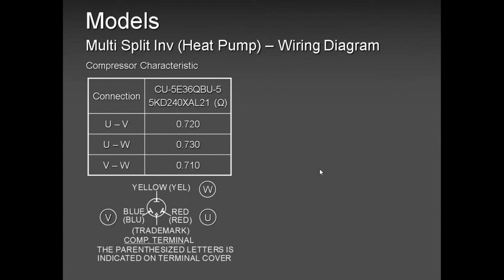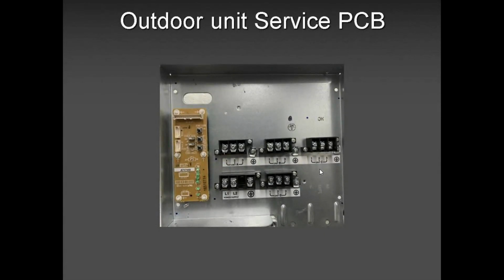When you have a problem, or when you think you have a problem with a sensor, just open up your app or your service manual, and you will see all these values. Take your multimeter, not an amp probe. Okay, don't use your amp probe meter. Use your multimeter. It will give you better, appropriate, correct readings, and compare them to the chart. Compressor. Many guys will call me and say, Paul, you are telling me the compressor is gone, but my readings are correct.